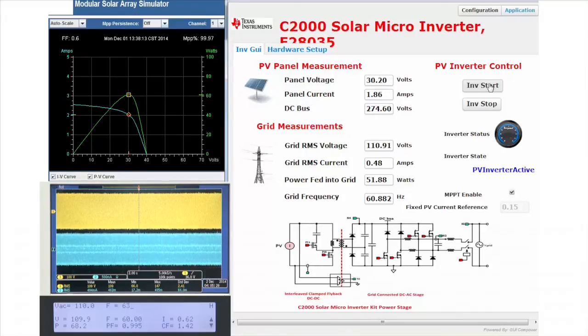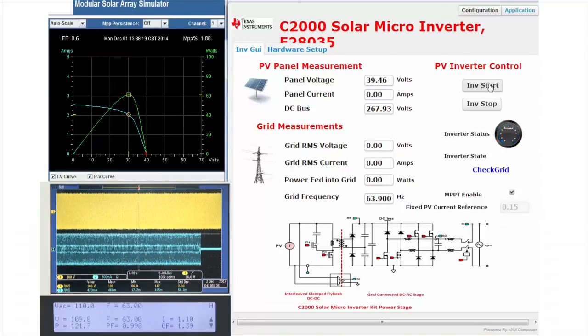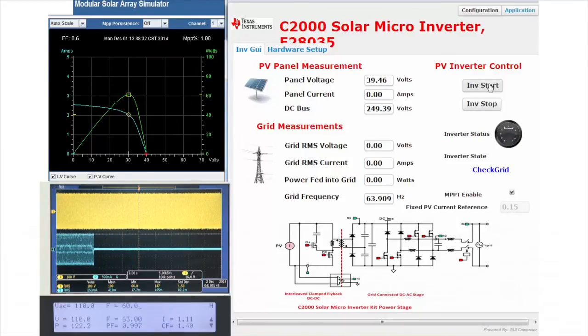First, let us change the frequency of the AC source to be 63 Hz. We see the inverter instantly shuts off. This is called over-frequency lockout. Now, bringing the frequency back to 60 Hz, we see the inverter starts up again as it detects favorable grid conditions.